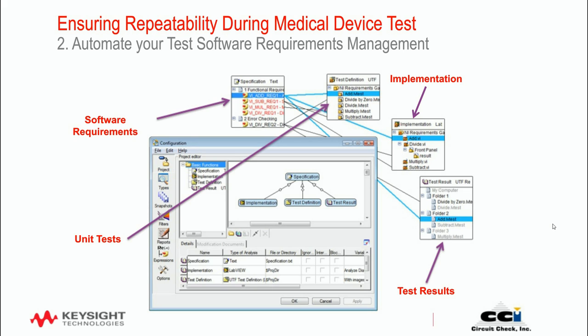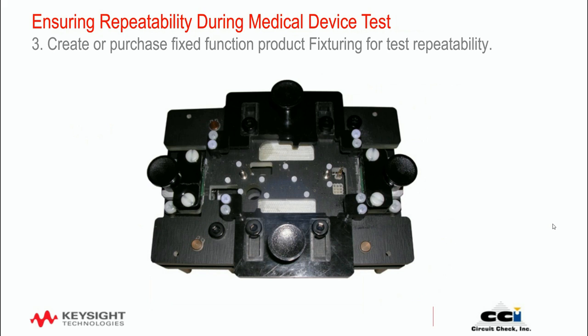From an interfacing perspective, in design and design verification you'll have a multitude of unit tests required to satisfy FDA guidance materials stating that the system should be challenged with abnormal inputs and conditions—the endpoints. So how do you achieve repeatability?